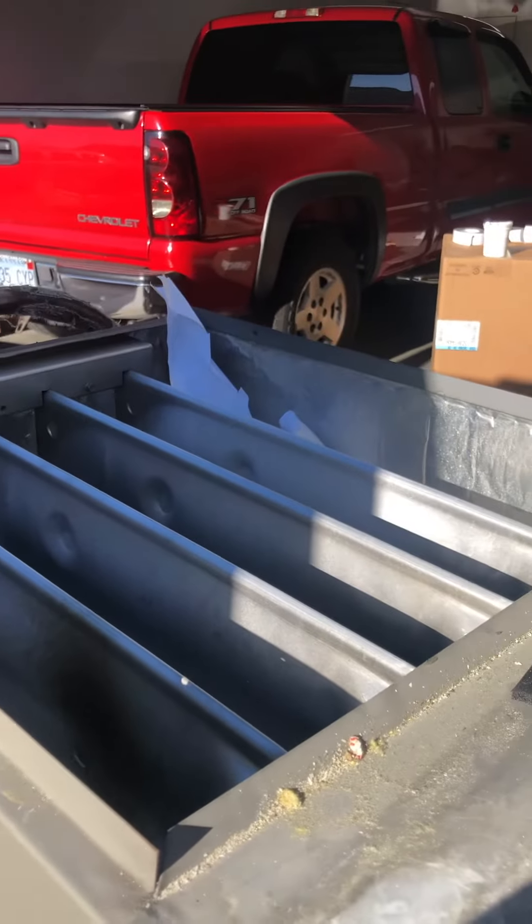You can see on this part as well — soot sitting right here. Heat exchangers do fail, guys, they do. And they're dangerous because all that exhaust was going right to your supply plenum and you were breathing all that. Yep, peace out.